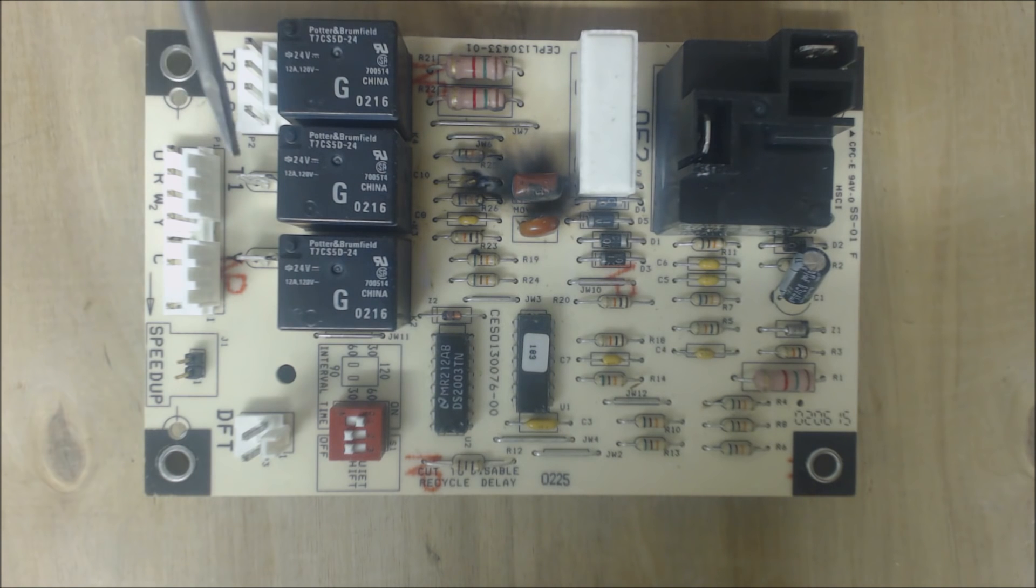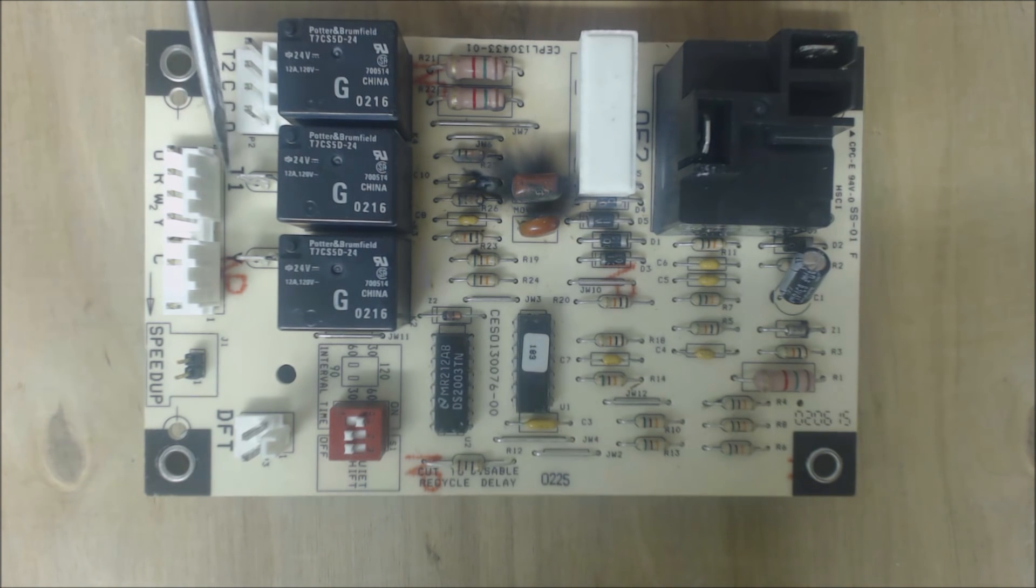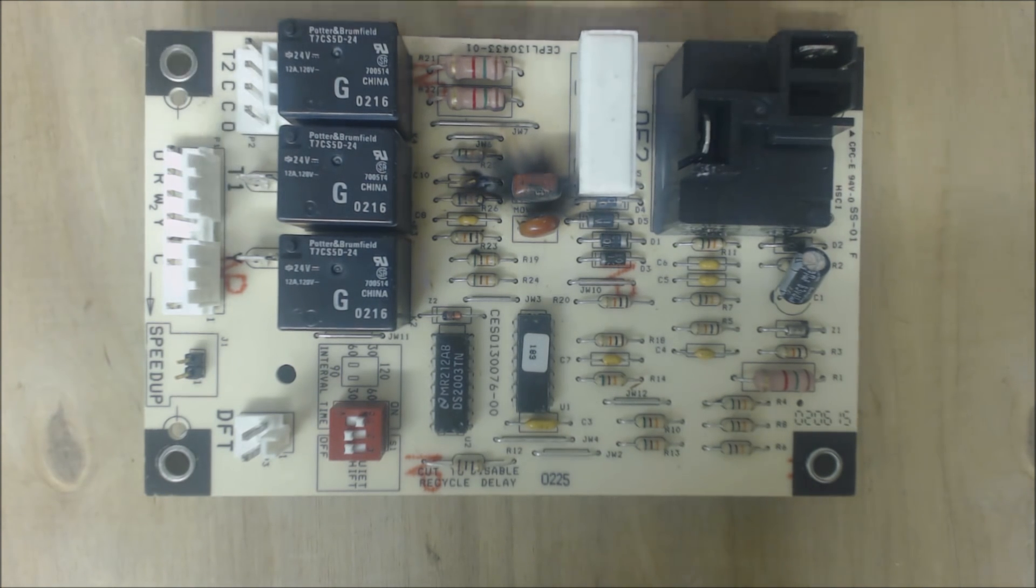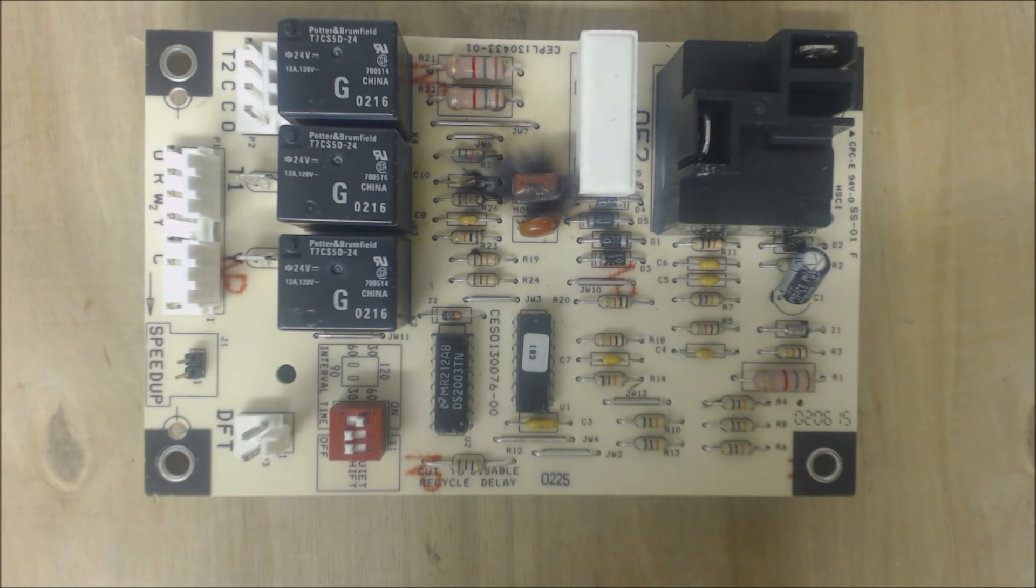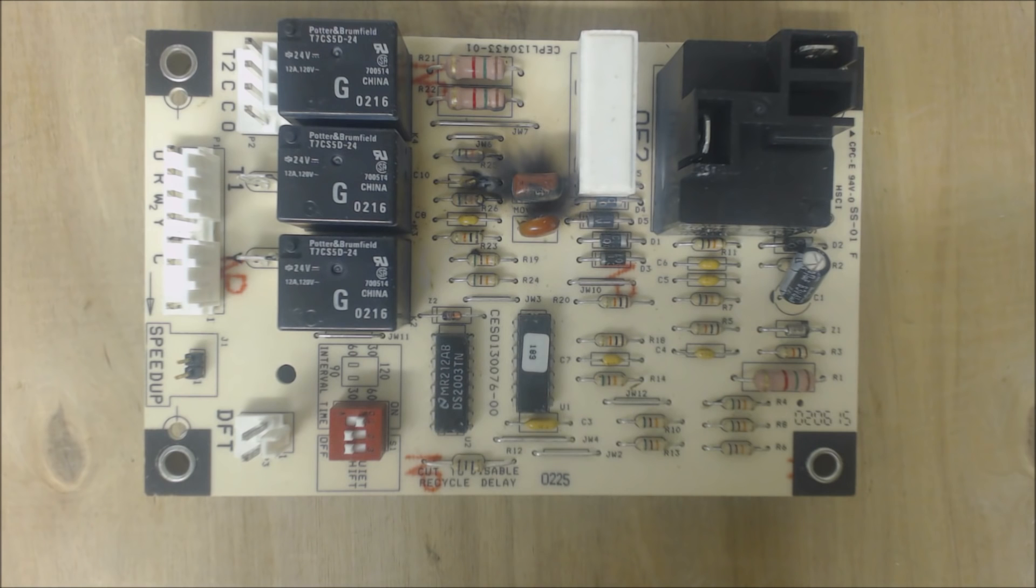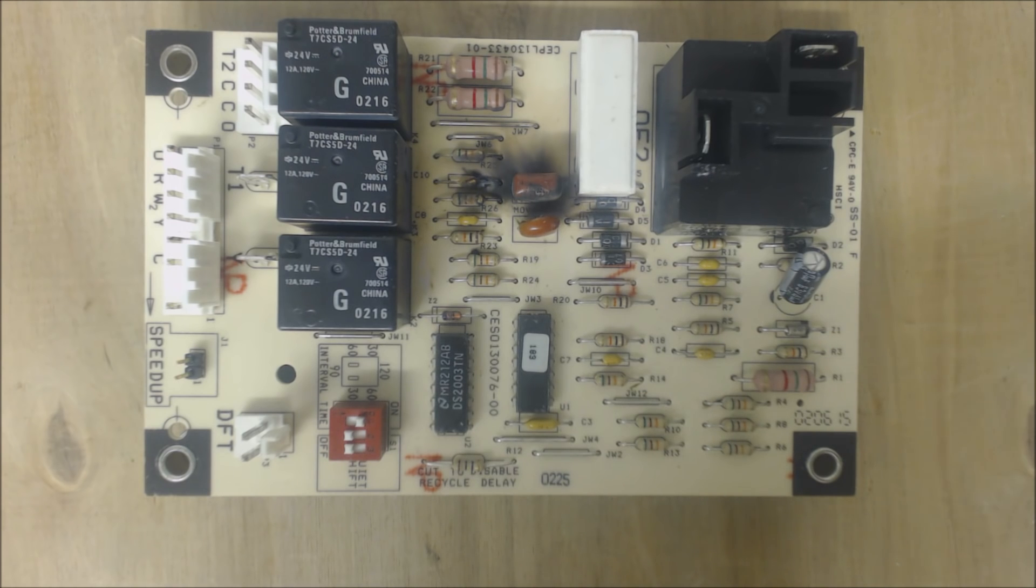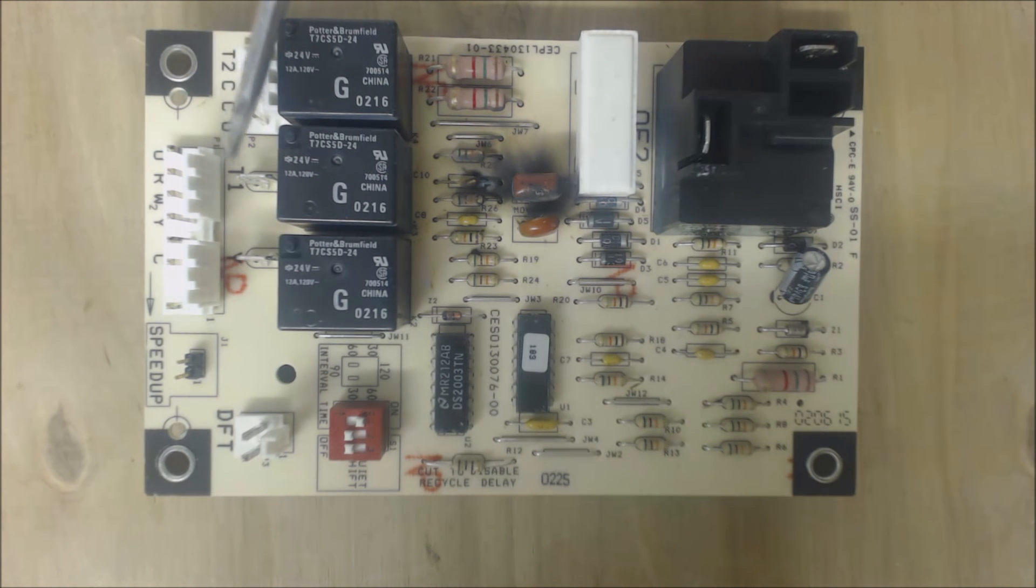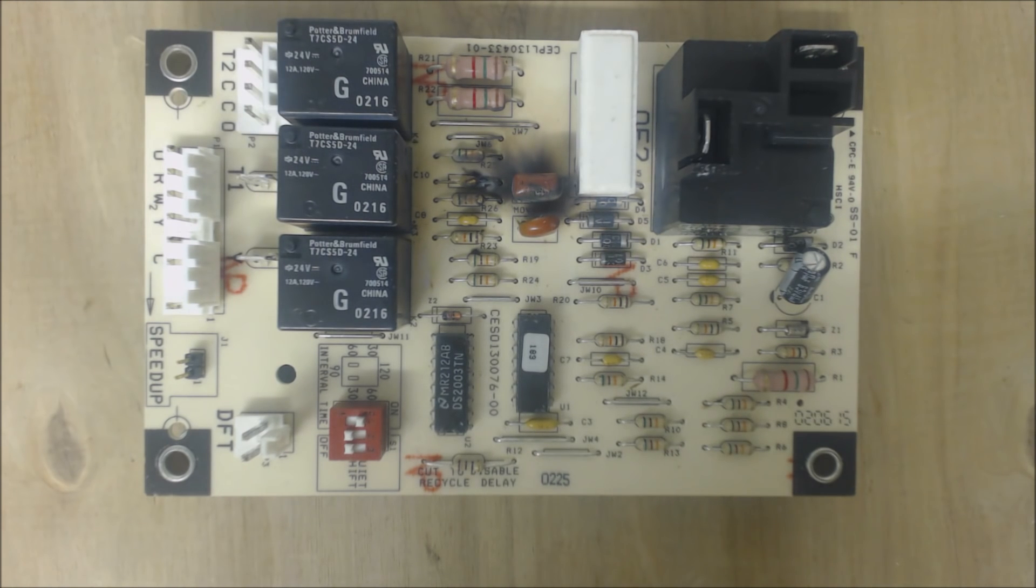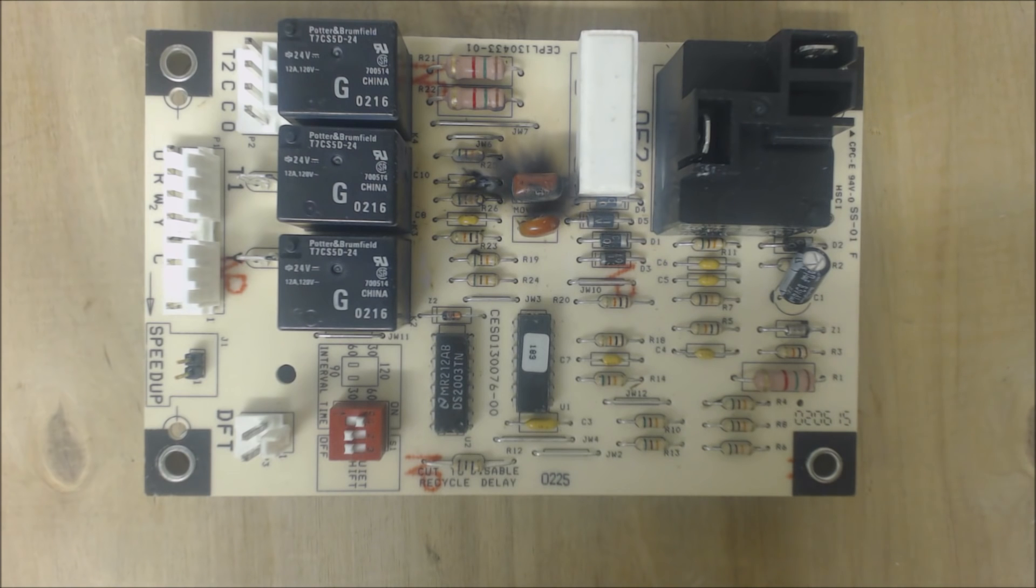Then you have T1 and Y. Going basically between those two terminals there is pressure switches and temperature sensors on the heat pump. So you have a low pressure, a high pressure, and then a high temperature. The high temperature will be found on the discharge line right out of the compressor. But if any of those are broken, it's not going to turn the compressor on. It's actually going to shut it off.